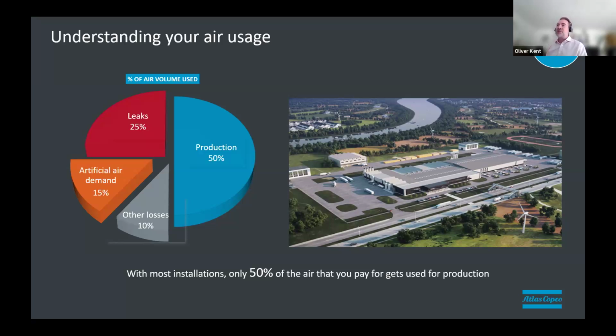Other losses could be a production machine that, when it's shut down, isn't isolated from the compressed air network and is still using compressed air even though it's not working. Also, inappropriate uses of compressed air. Maybe there are devices that are using compressed air that could use another power source. So you can see, out of our total 100% air generation, approximately only 50% of it actually goes into useful production.